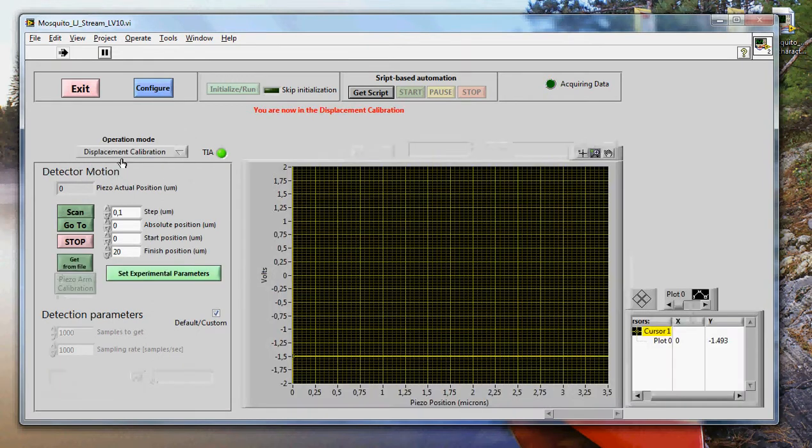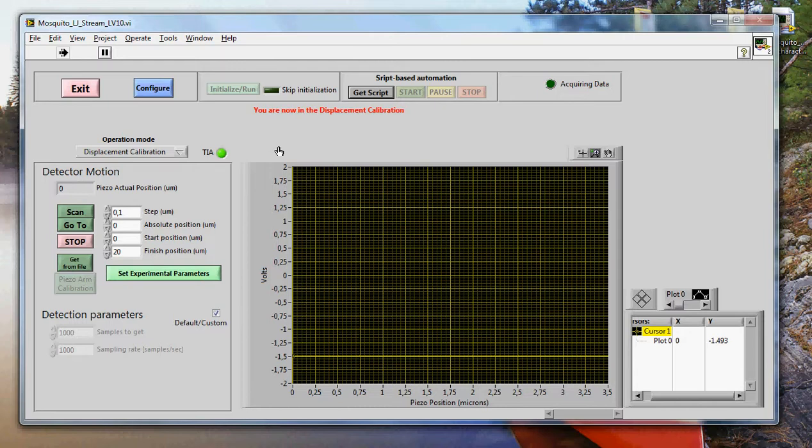Let's now go to the displacement calibration mode. The displacement calibration mode, or operation mode, is the mode where you map the displacement of the tip of the transducer into voltage. So this is what enables you to calculate, basically, the force that acts on the transducer, or the displacement of the transducer based on the intensity of the laser that comes back from the transducer.